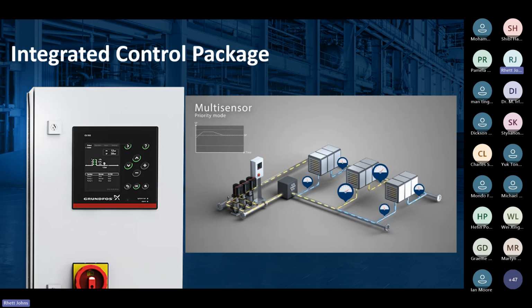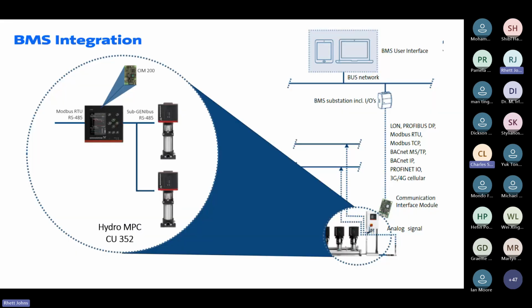Using this method, we can ramp up and ramp down the pumps and ensure that at every single stage, we're able to match and meet the pressure requirements within the system and the demands of those individual zones. If you merely have maybe one sensor on the discharge side, you could end up with a system that is very slow to react to drops in pressure and a poor performance for the users within that system. And this is running autonomously as well, isn't it, Rhett?